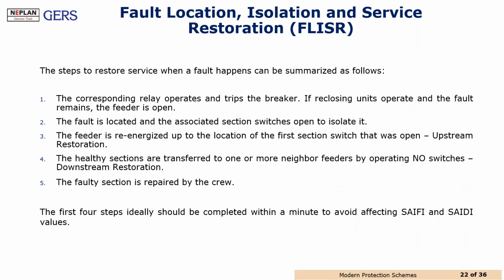Well, another modern protection system, and this is not a protection system specifically, but fault location, isolation, and service restoration, is one of the advanced applications that we find in smart grids. Because fault location, isolation, and service restoration, known as FLISR, allows us to implement proper strategies in order to reduce the time during which energy is not being supplied, and to increase reliability by opening and closing the corresponding breakers on the distribution networks in order to extend the operation of the system.